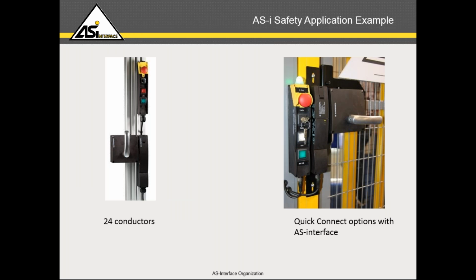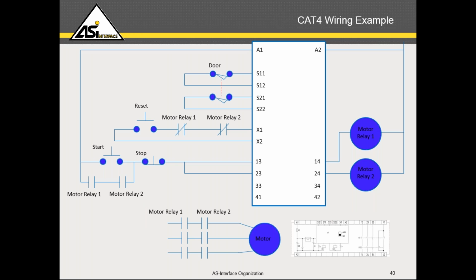Then if we take a step forward, in the example that we saw, we had 16 door interlocks, and as soon as we add the locking interlock, with the combination of the control station, we are looking at 24 conductors that you would have to wire back into your main panel. So you first need a large multi-conductor cable, and that has to run back into the panel. The cost is enormous. In that case, when ASi Safe is used, the implementation becomes much easier, because you have a quick connect solution with a 4-conductor cable that goes onto the ASi flat cable. So it becomes a very simple solution given the complexity in the examples that we saw.